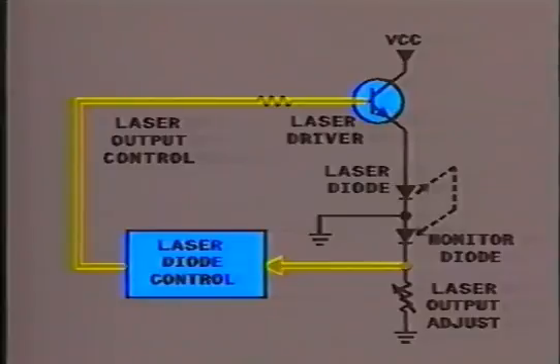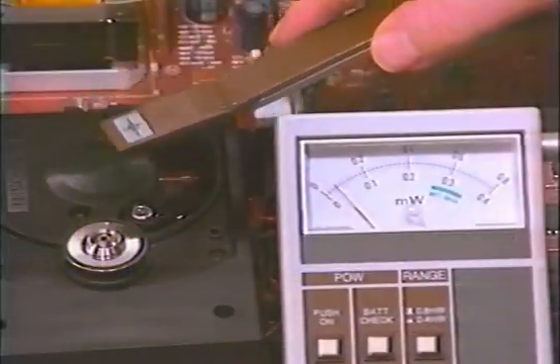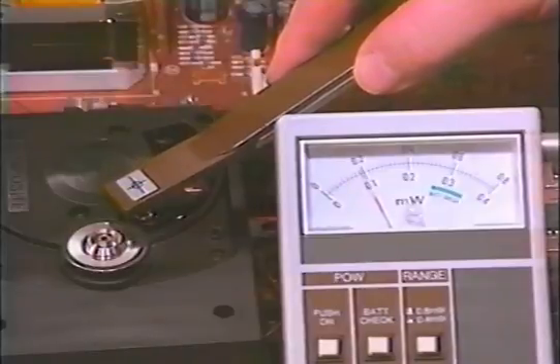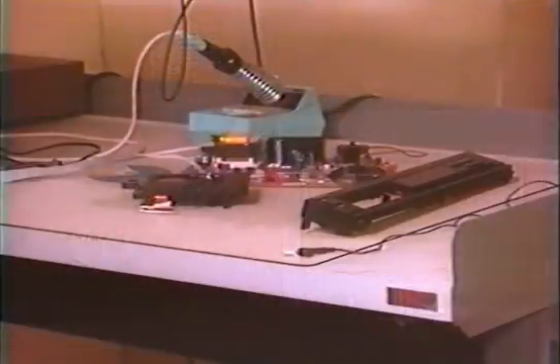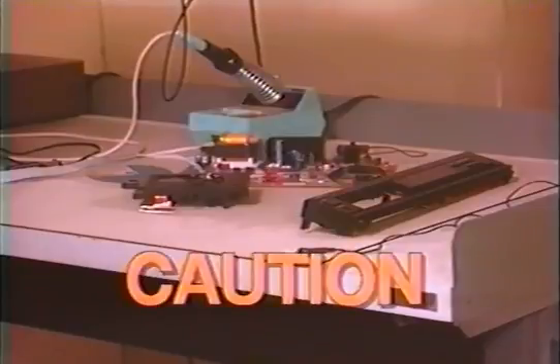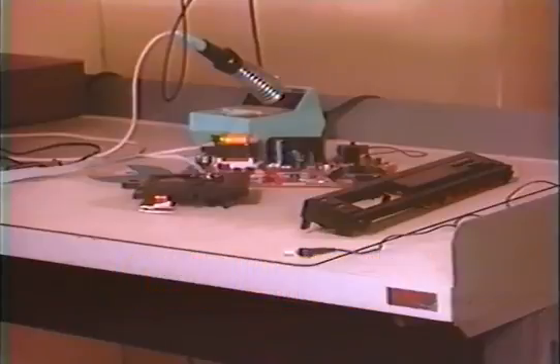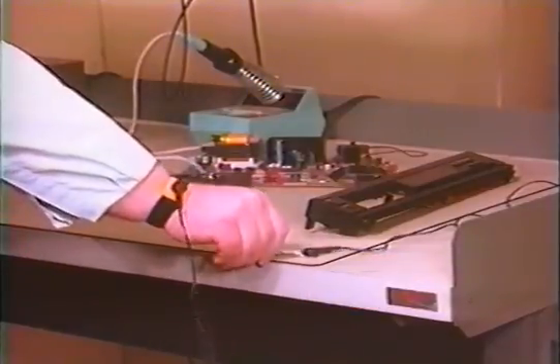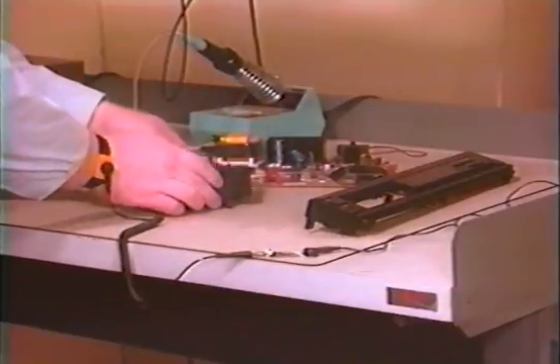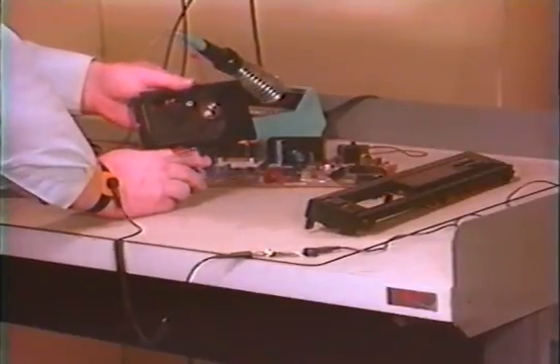In some optical pickup systems, a laser output control is included to adjust the laser output to its nominal level. Refer to the manufacturer's service manual to check for adjustments and output levels. Care should be used when handling optical pickup devices. The devices may be damaged by electrostatic discharge if not properly handled. A grounded ESD protected mat with ground strap and grounded equipment must be used when handling ESD sensitive devices.